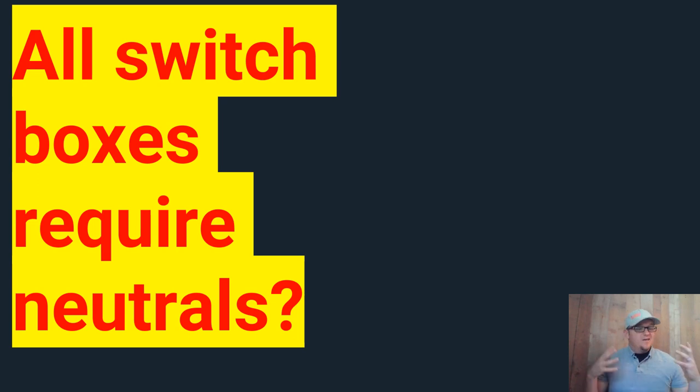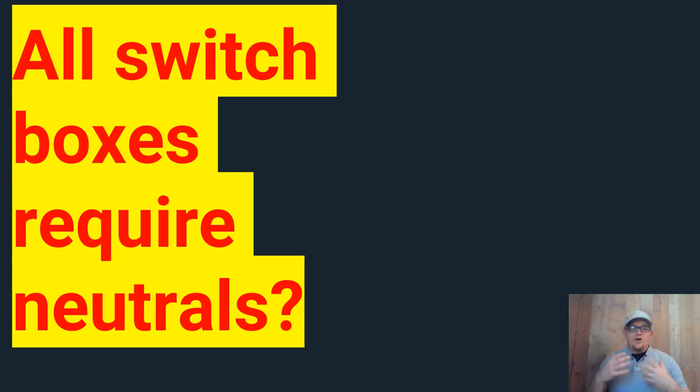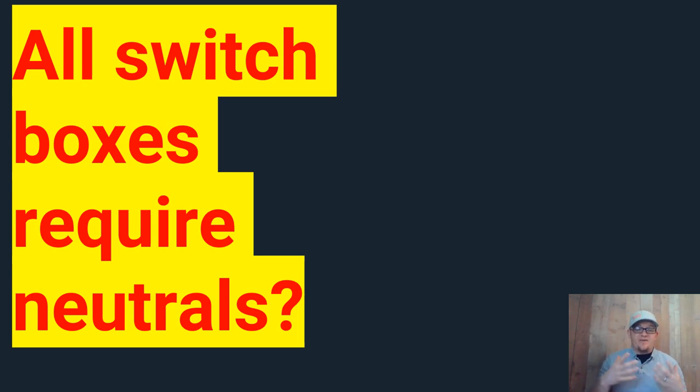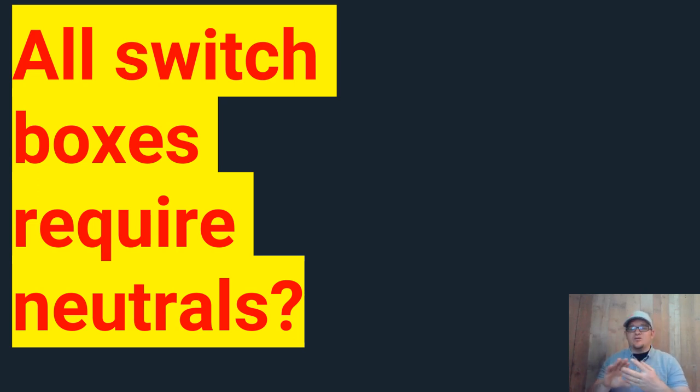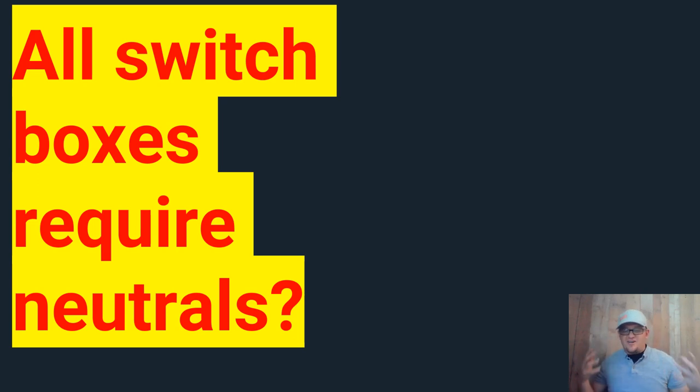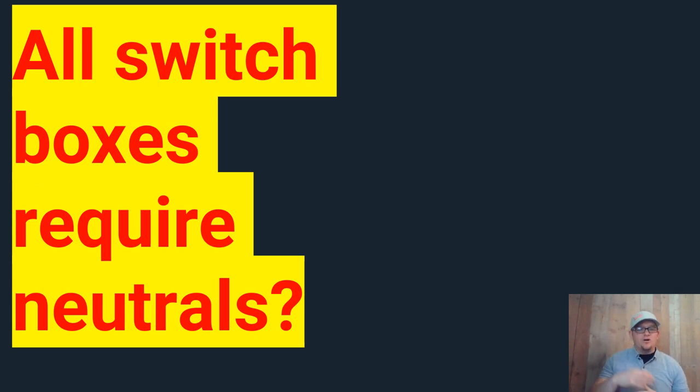Well, sorry to burst your bubble, no you don't. You don't have to have a neutral if you can hit any of these points. So what the code is wanting us to do is provide a neutral for these new electronic switches, electronic dimmers, all these different things that may require a neutral. Or anything like the new switches that control fans or anything like that that may require a neutral.